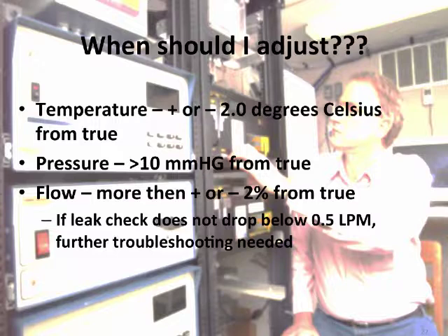There's also the new tape that we're getting, the flat box tape, that doesn't seem to shed on the gate anymore, but that has higher leak values than the old tape used to. I noticed 0.4 is about normal. Really? Okay. And so that may be a contributing factor. I didn't realize we were using new tape.